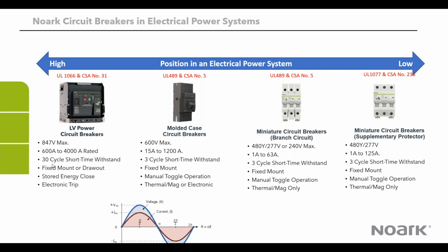So basically what we're saying here is that this air circuit breaker can withstand 30 cycles, which is the maximum it can withstand in an electrical situation. A cycle is just the time it takes for the voltage or the current to go from the positive half cycle all the way to the negative half cycle. That's one cycle. Because in North America we use 60 hertz, that is roughly 16.7 milliseconds for one cycle. So if the air circuit breaker can withstand 30 cycles, you multiply that by 16.7 milliseconds, and that gives you roughly 500 milliseconds, which is still less than half of a second. So for half of a second, the breaker is able to withstand the particular current withstand rating that it has been tested for.